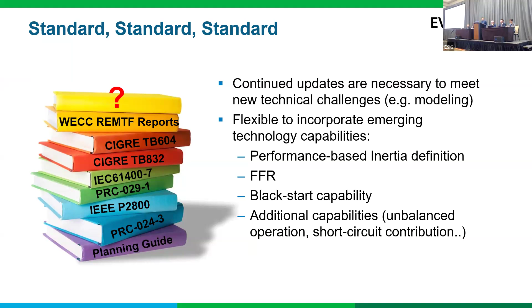Another challenge we have observed in our studies and projects is transparency. The limited visibility of models has been affecting our projects. What happened is the ISO doesn't know too much about the developer's black box model, and the developer doesn't know too many details of the grid. In one project, the ISO discovered stability issues which we couldn't reproduce, because it was a stability issue in the actual system due to interaction between the plant and an external device in the grid.